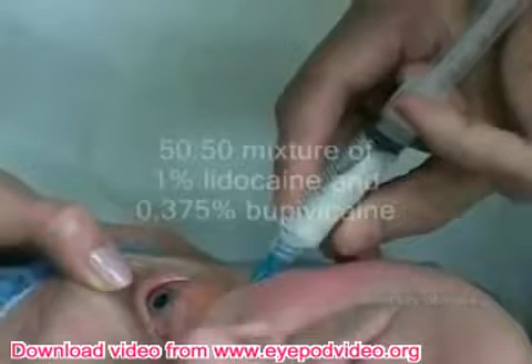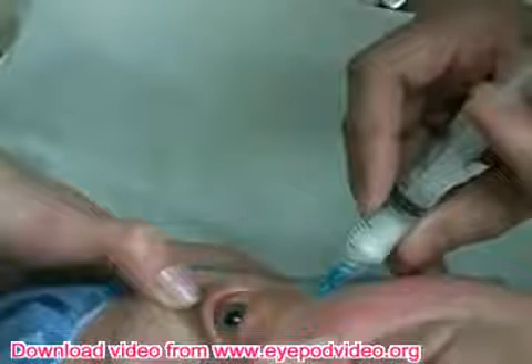Prior to starting the CPC, a retrobulbar injection of anesthetic comprised of 1% lidocaine and 0.375% bupivacaine is given. The non-operative eye is patched for protection from the laser. Once good anesthesia is verified using tooth forceps, a lid speculum is inserted between the lids. Protective eyewear should be worn prior to starting the treatment.